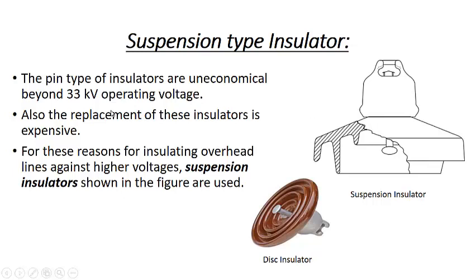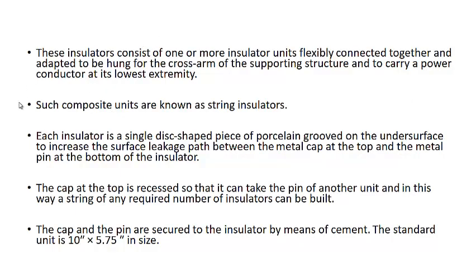And in the case of a pin type insulator, such flexibility is not there. In that case, we have to replace the whole 33 kV pin insulator unit. Such composite units are known as string insulators because they are combined to form a string of disc insulators. And in short, they may also be called string insulators.